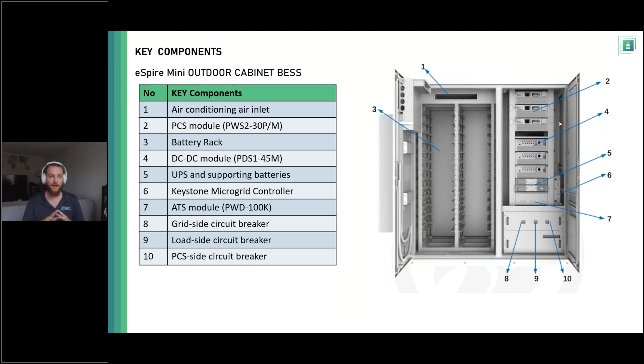Like I said, this has the same exact microgrid controller and the same software that we'd be using for the larger system. So now I want to show you what that looks like. But actually first, that was just a rendering, right? This is an actual picture in our lab of a fully loaded unit. So this would be 266 kilowatt hours, up to 90 kW of inverter power, up to 135 kW of DC coupled solar. It also has a UPS in the unit to handle black start capabilities, and all the breakers, load side, grid side, inverter side that you would need to make this system operate.